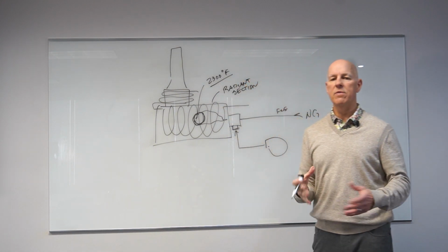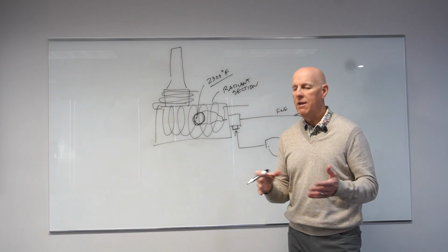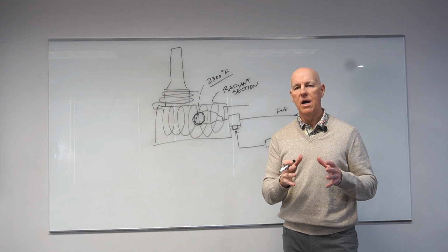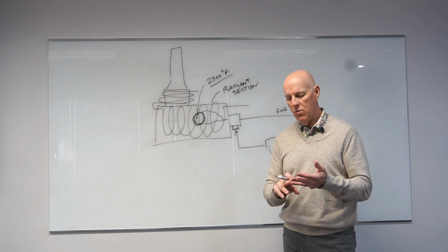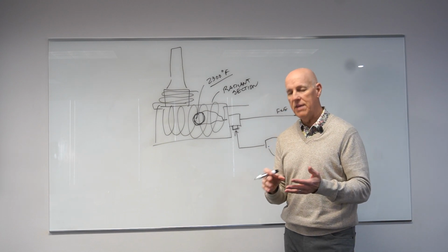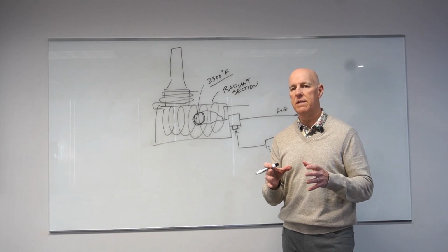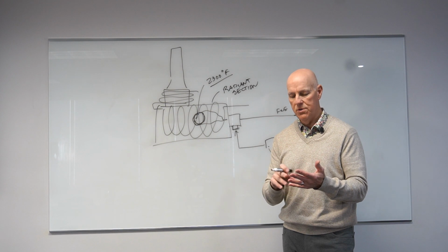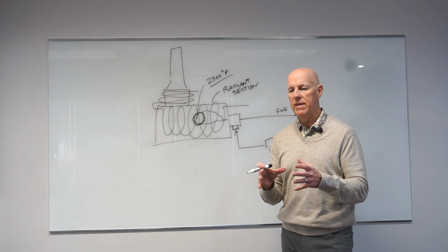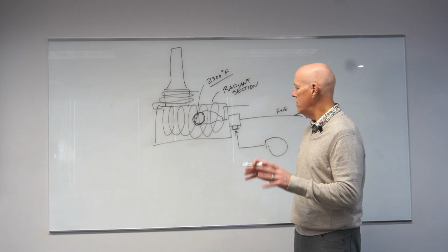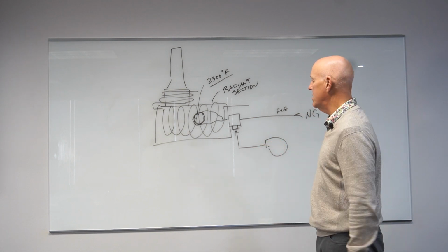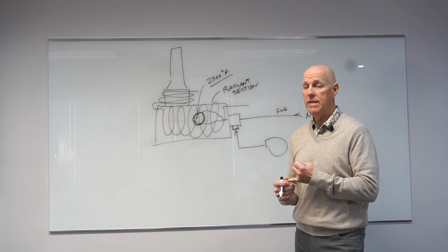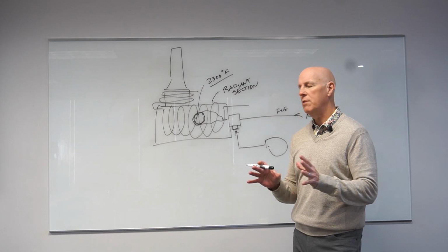So when we have a waste gas that we want to destruct, basically that means we need to burn it. We're trying to burn it to get it to compounds that are safe, like CO2, water, SO2, safer compounds than the state that it's in. Because the state that it's in, it may have some bad actors in it, like H2S or some heavy hydrocarbons. So essentially you're trying to burn or oxidize it. To do that, obviously I need air, I need oxygen, and I need a high temperature environment.